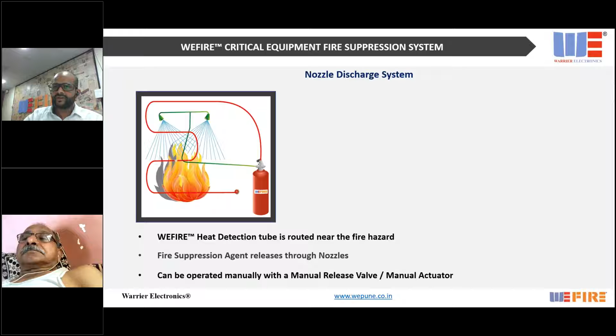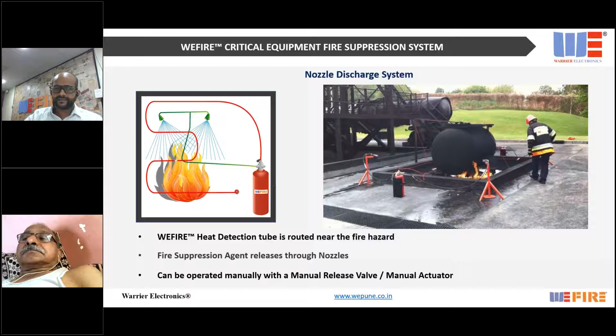So here we have two cylinders, one on this side, one on the other side, and we have 4 nozzles on each corner, and the detection tube is routed inside the pit. Now we'll light a fire. Here we are using a dry chemical powder as the agent. This is good for open areas where there could be a little bit of wind, and powder is the ideal agent for such locations.